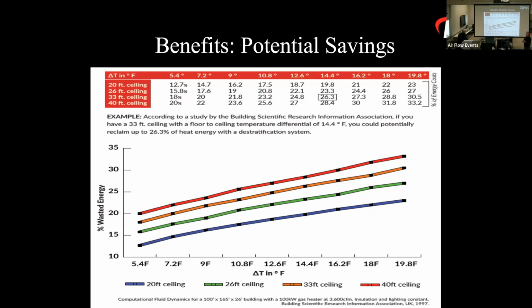When we put out there the savings for basically the heating and destratification, because destratification is still number one for us. That's the main savings that we typically get, because if you've got an equalized temperature within that thermal envelope, you can set that thermostat back. Anytime you set back a thermostat, you're going to save energy. It's just going to happen. This is a study that they did for us a few years ago and actually came up with this data. We can provide this. I have this information and can send it out if anybody wants to see it.